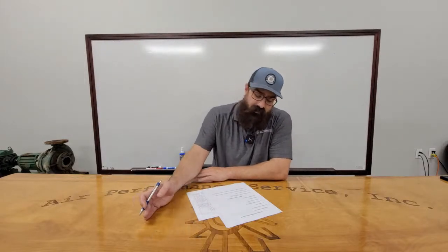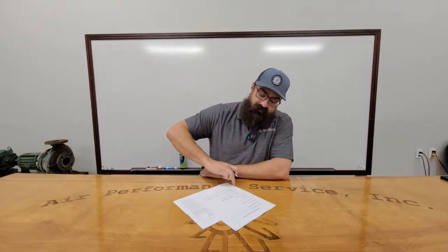Next would be a little bit more detailed. We'll do single zone water source heat pumps. Same basic theory and principle of operation for the cooling side of things. In most control systems, as your temperature gets beyond or close to set point, you will engage your cooling. Depending on if it's single stage or multi-stage, the further or closer you get to set point, you will stage up and down. The one thing you have to consider with a water source heat pump in our applications is the condenser loop side of things. They're pretty simple. Usually most building automation systems are not tied into the status of a water source heat pump, or you have a system that is standalone heat pumps with a controlled tower.